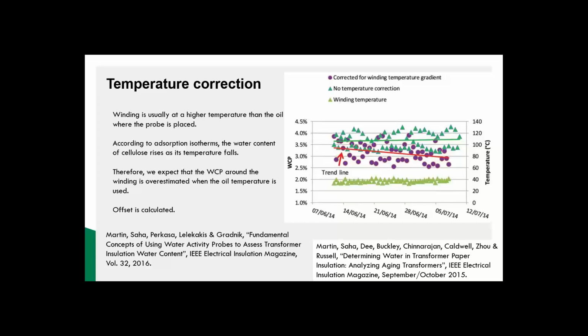So there's two ways of doing the dielectric response. Either we've let it cool to ambient temperature, and then we know what the temperature of the winding is, or we might disconnect it and run the measurements and note down the temperature indicator. Now, nearly always in an operating transformer, the winding is slightly warmer than the oil. So that just means when we put these probes into the oil, the actual probe might be measuring a slightly lower temperature because the oil is slightly cooler than the winding.